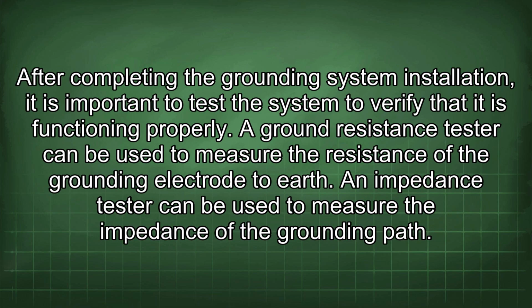After completing the grounding system installation, it is important to test the system to verify that it is functioning properly. A ground resistance tester can be used to measure the resistance of the grounding electrode to earth. An impedance tester can be used to measure the impedance of the grounding path.